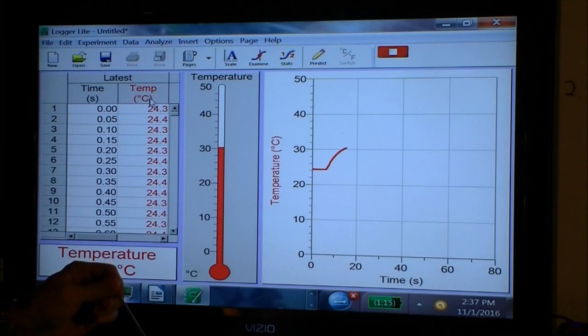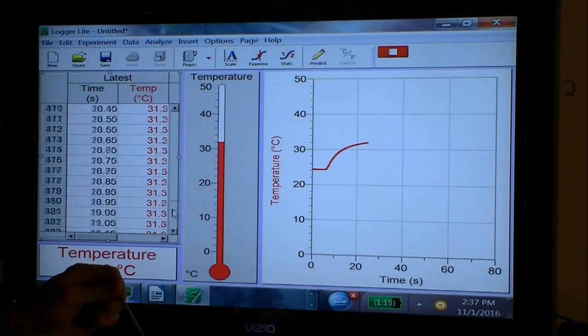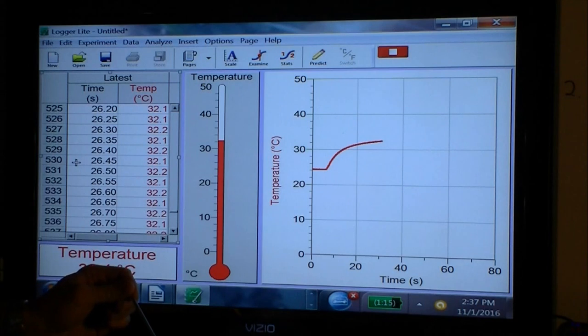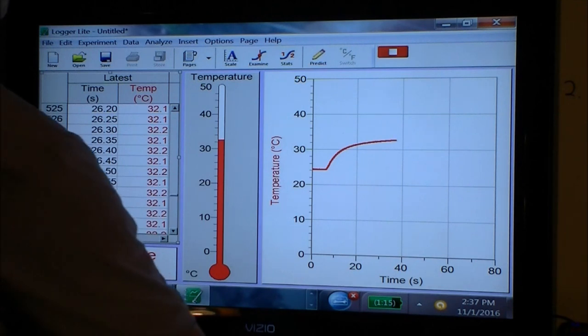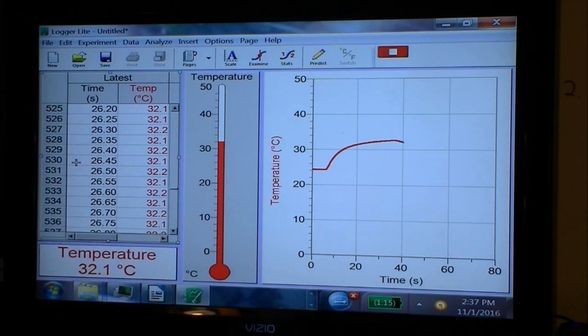So if we wanted to, as it's doing this, we can go ahead and scroll down, and you can see that the time interval is 0.05 seconds now, and 0.05 is a 20th of a second. And it's accruing new measurements at that rate, and it'll probably keep going at that rate for the number of seconds that we set it to, which I think was 60. And then if I let go, it'll come back down. Alright, so this is interesting, and this is how the temperature sensor works. And it's also how you can set the sample rate for any number of measurements that you might be interested in. Okay, so let's go ahead and let it finish.